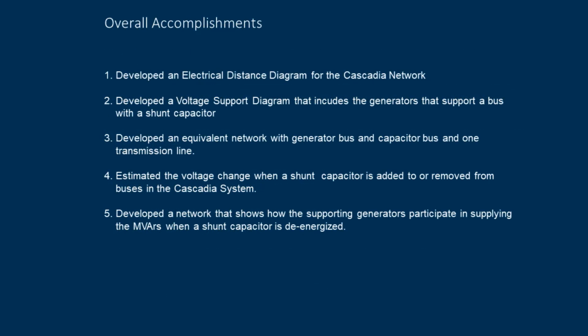Let's summarize what we've accomplished in this module. We started out and developed an electrical distance diagram for the Cascadia network. All the lines of different voltage levels, 500 and 230 kV, were transformed to an equivalent single circuit 230 kV line distance. We then showed how to develop a voltage support diagram that just includes the generators that support a bus with a shunt capacitor. We then showed how we could build an equivalent network and reduce that to a simple network with just one generator bus, one capacitor bus, and one transmission line.